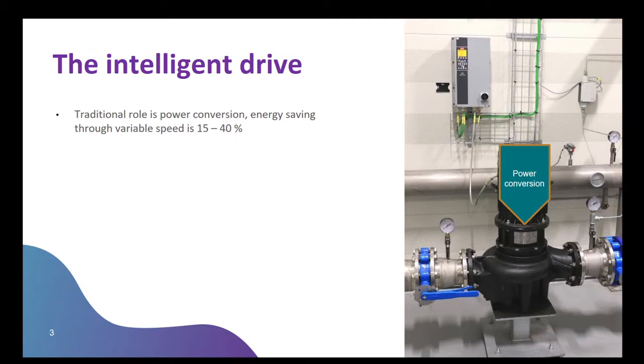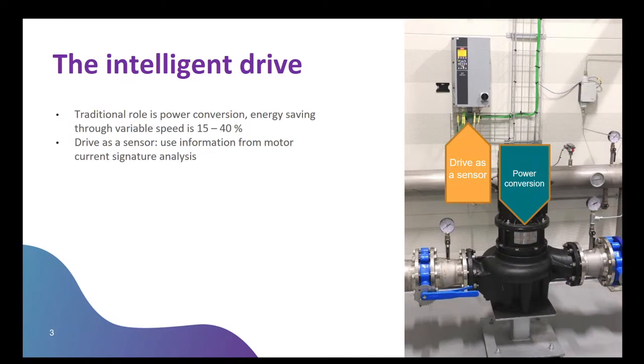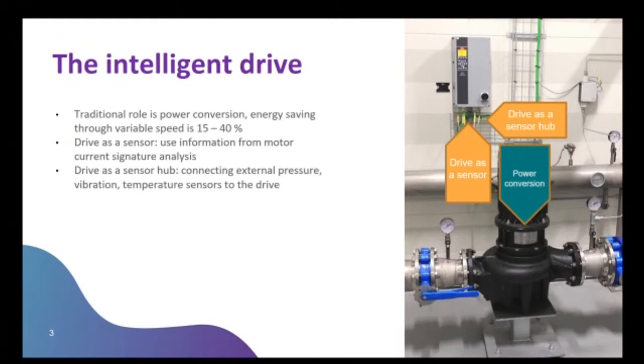But what comes now is a change in the role of the drive by adding new opportunities through digitalization. One of the roles is to get information from the motor through analyzing the motor current. And this concept we call drive as a sensor. So by analyzing the motor current, we can sense a lot of information from the application. Then you can see in this picture a lot of sensors. These sensors, pressure sensor, temperature sensor, other kinds of sensors, can be connected directly to the drive. And this concept we call drive as a sensor hub, because the drive is already in the installation, it already has the connectivity and it has the possibility of processing these signals.